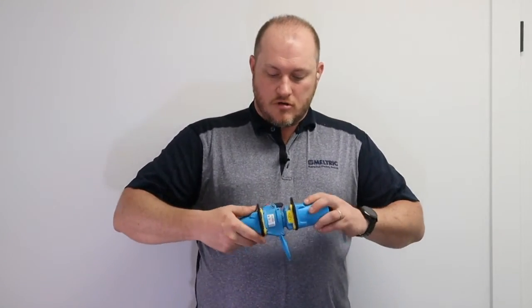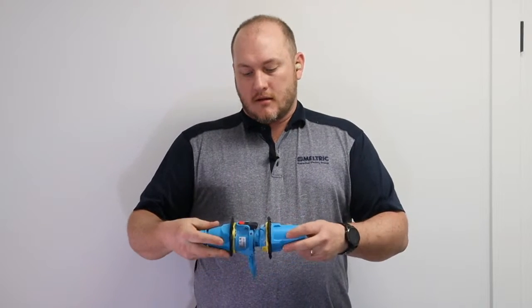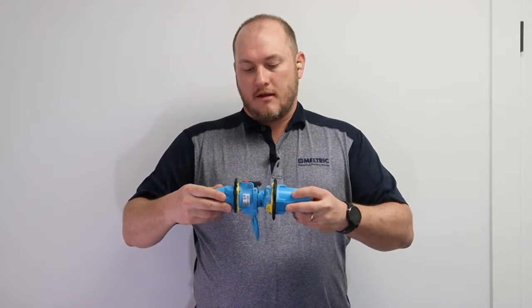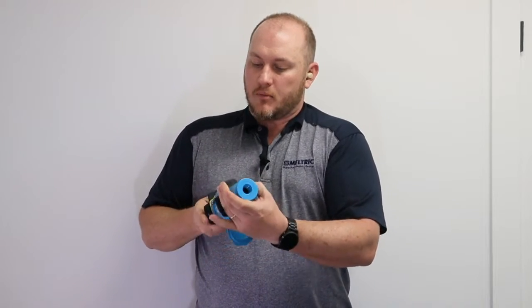So that's the coordination between your overcurrent protection device and your plug and receptacle, being able to make sure that the device itself can handle closing on a fault, because you will have some potential arc flash capability. One of the things that's interesting about some of the operations, this is a really interesting thing in my opinion about the difference between a pin and sleeve and a Meltric plug and receptacle, is when we go together, you actually have to do a short little rotation in order to open and close that shutter. So we rotate from about the 10 o'clock position to the 12 o'clock position, and that opens the dead front shutter and aligns our contacts.